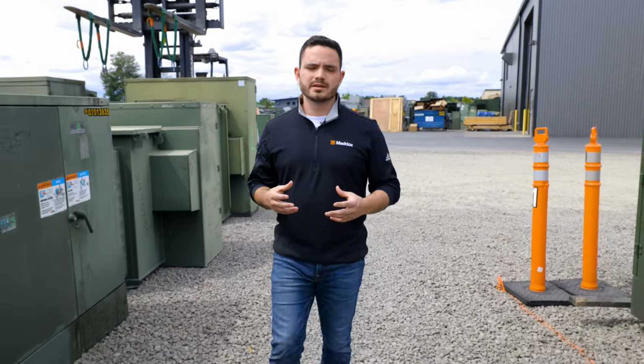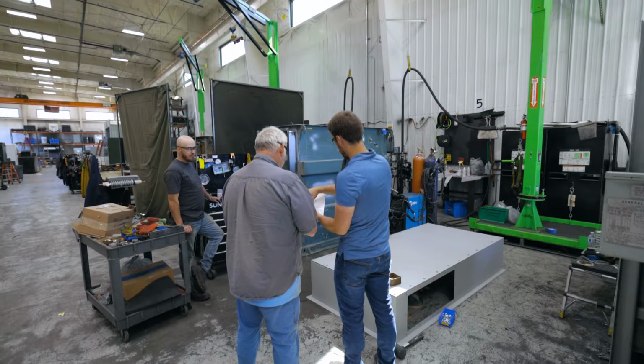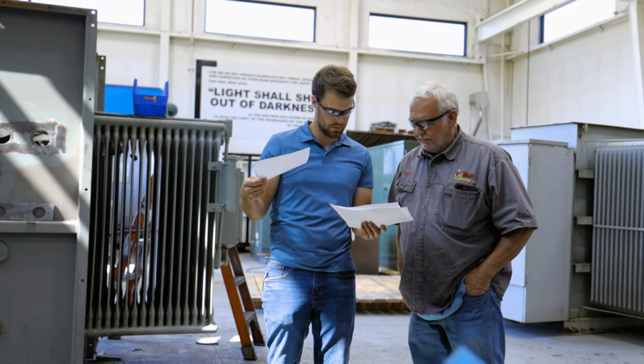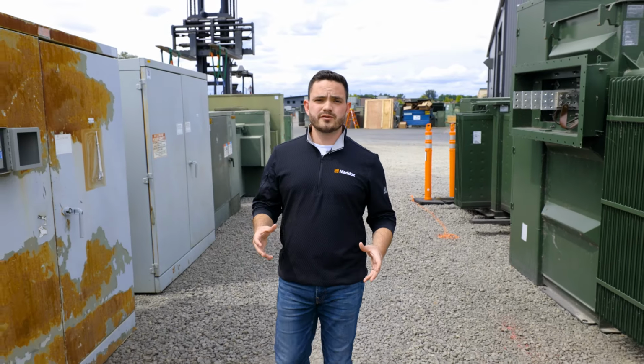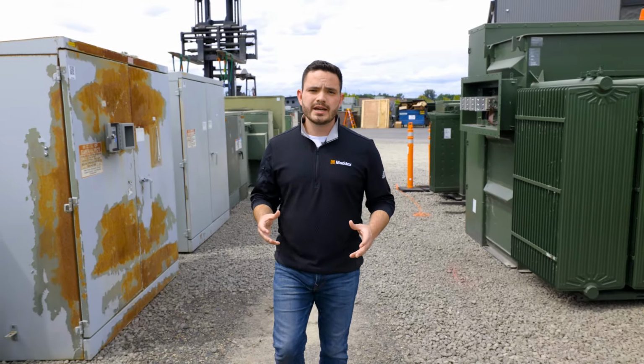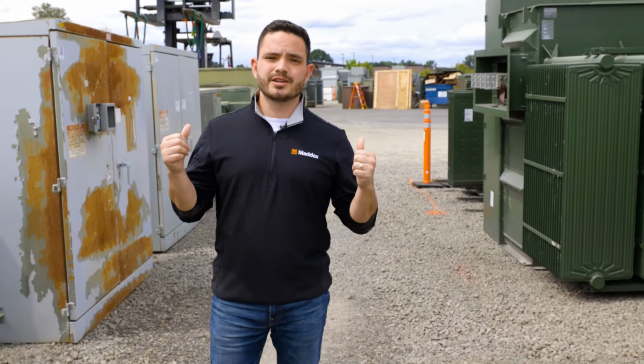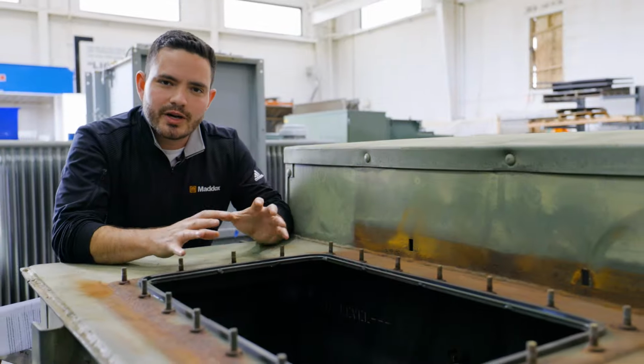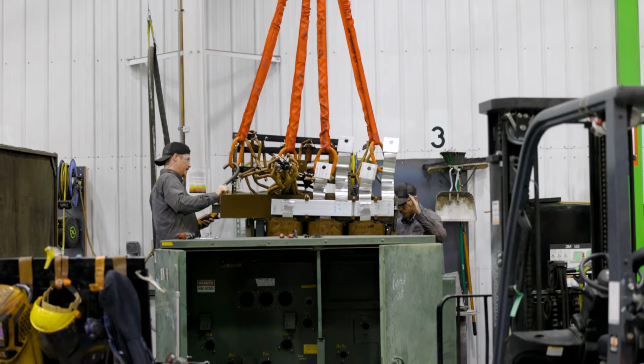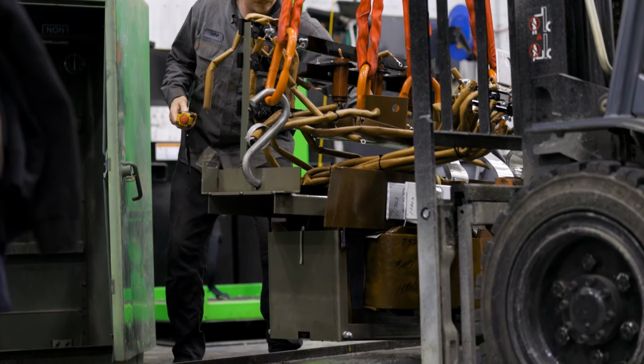After incoming evaluation, the transformers are placed in our secured storage yard, waiting to be sold. Because we inventory everything so meticulously, our engineering team can reproduce CAD drawings for any unit in inventory. Once we have an order on a transformer and the drawings are approved, they're taken back into the shop and the reconditioning process begins. The first thing we do is remove the transformer lid and take the core and coils out if any internal modifications are needed.